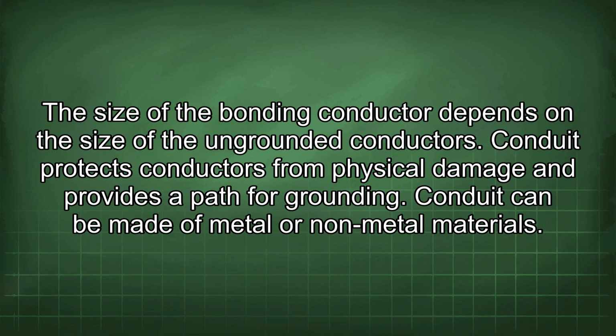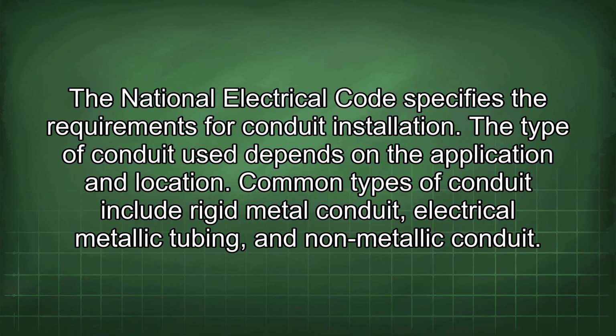Conduit protects conductors from physical damage and provides a path for grounding. Conduit can be made of metal or non-metal materials. The National Electrical Code specifies the requirements for conduit installation. The type of conduit used depends on the application and location. Common types of conduit include rigid metal conduit, electrical metallic tubing, and non-metallic conduit.